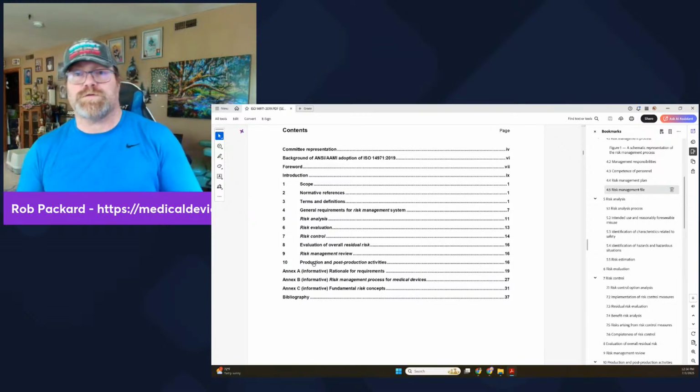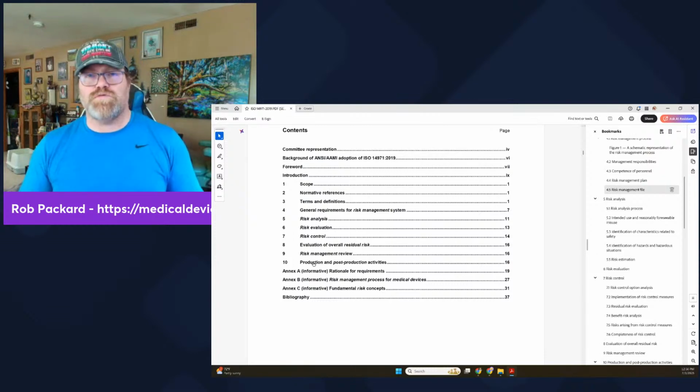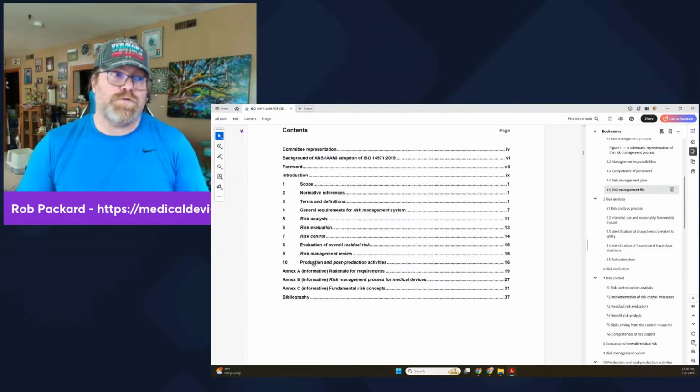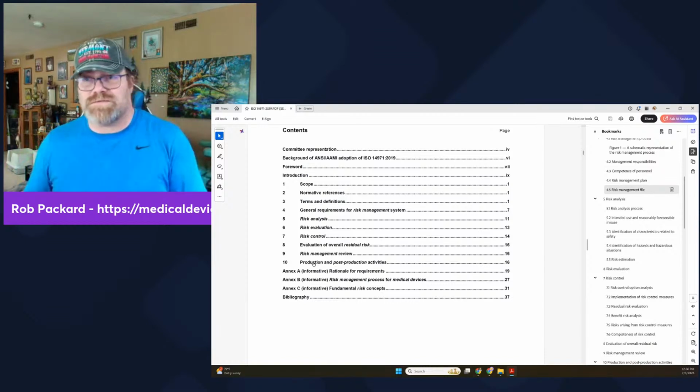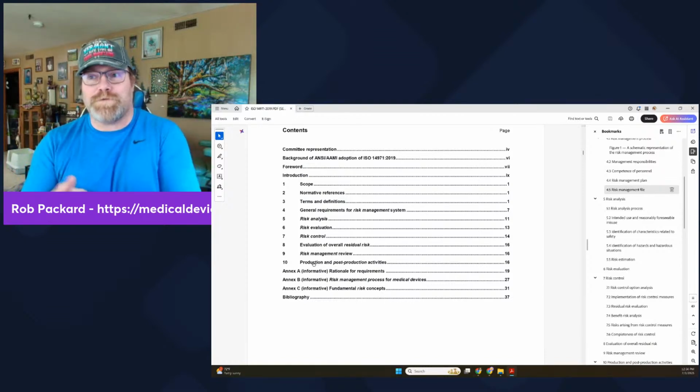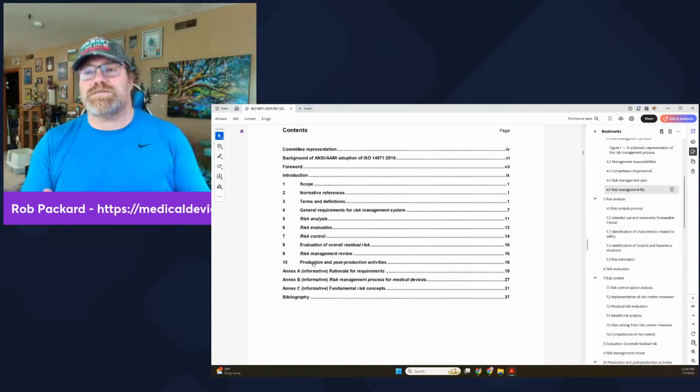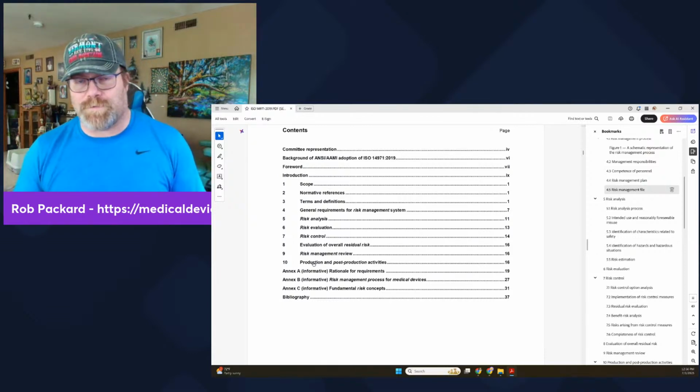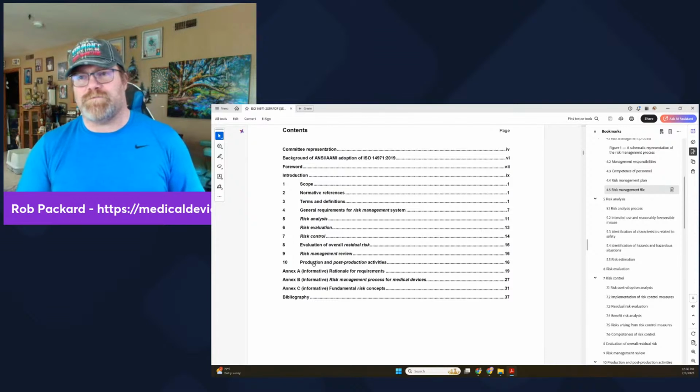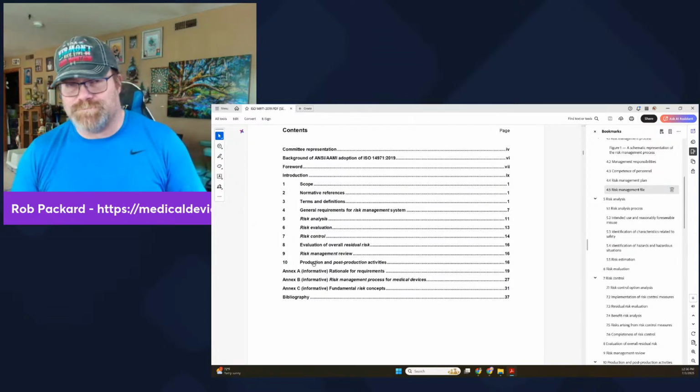It's required for Europe. It's required for de novo. It's required for PMAs. It's not required for low risk products in the US that are class 2 that already have a predicate. But, we already know those are acceptable because they're already on the market. They're ubiquitous. They're everywhere. The blood pressure cuff, we already know that's on the market. So we know the overall residual risk is acceptable. So that's why you don't have to do the benefit risk analysis for those. But if you're doing it for Europe, you have to do it for everything, no matter what.